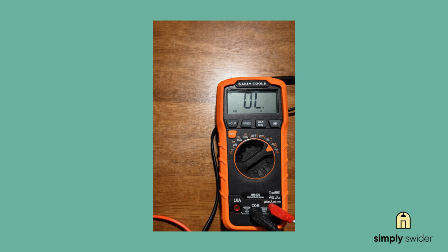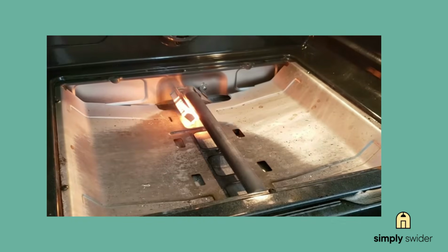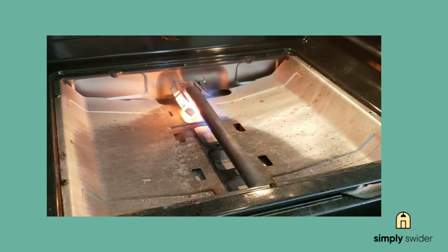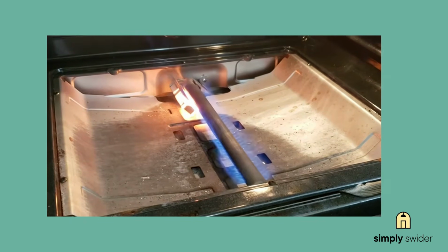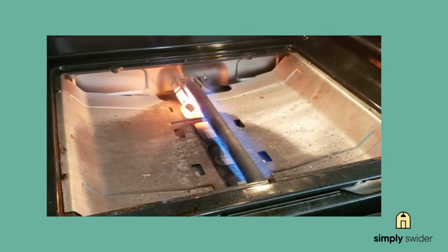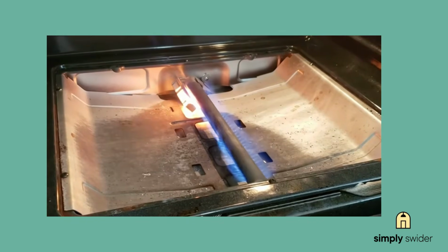The fix is straightforward. Replace the igniter. Now here's something most people don't know. When you install the new one, don't touch the ceramic with your bare fingers. The oil from your skin creates hot spots that'll make it crack prematurely. Use gloves or handle it by the metal bracket only.